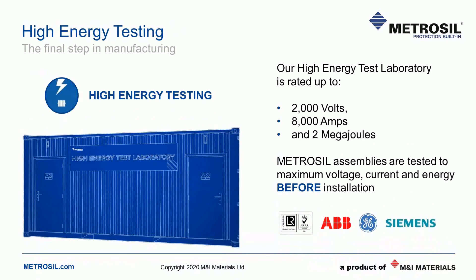Our final manufacturing stage is our rigorous testing. Something very special and unique to Metrosil is HETL, our high energy test laboratory, which allows us to put our excitation protection assemblies through the worst-case scenario for an overvoltage. If a customer tells us the maximum current and energy values and a protection voltage, we can demonstrate that the unit can handle the energy while keeping the voltage at or below the safe maximum. Not only are we audited by ISO auditors, we are also audited by the OEMs who visit our factory, including ABB, GE and Siemens. ABB awarded us ABB critical supplier status and GE acknowledged us as a class A supplier.